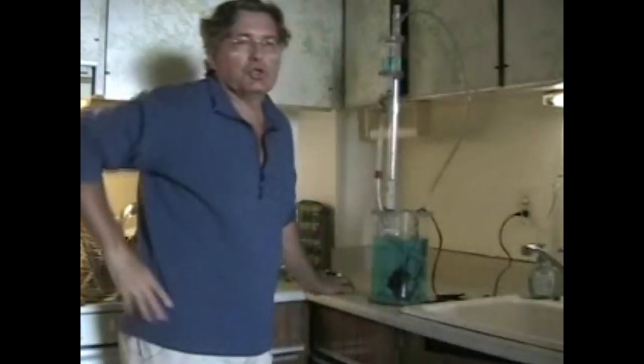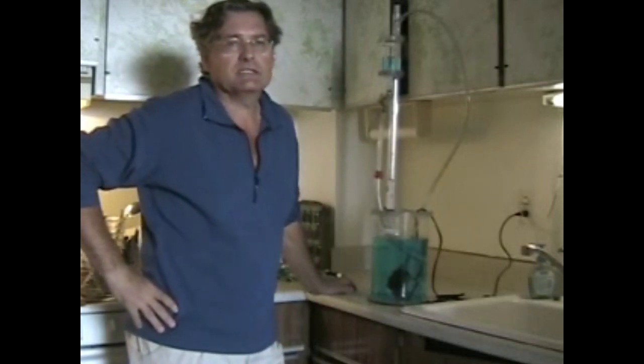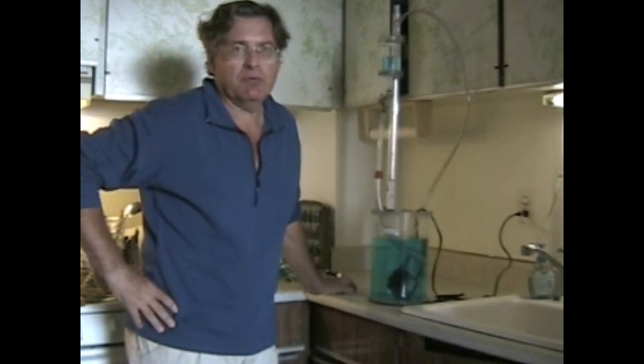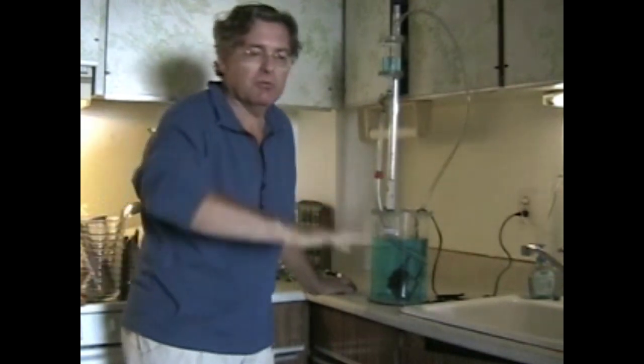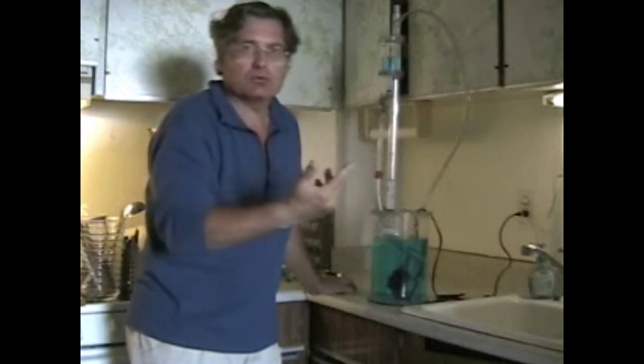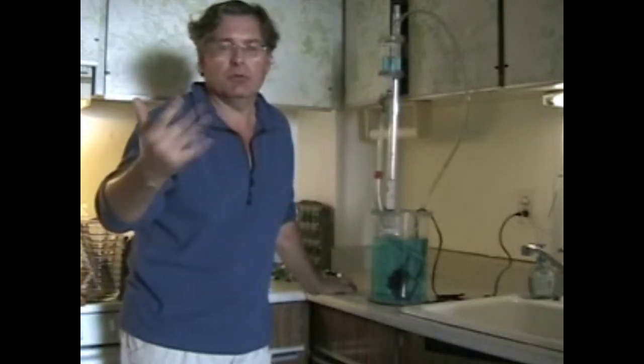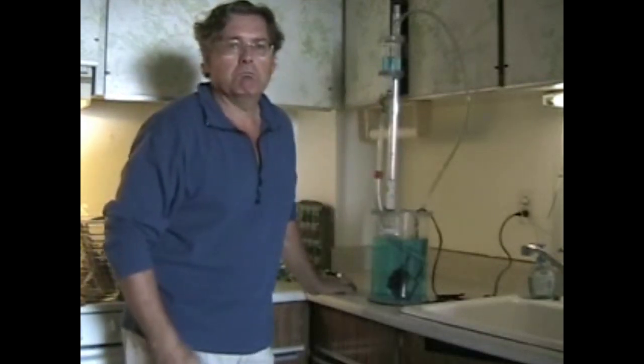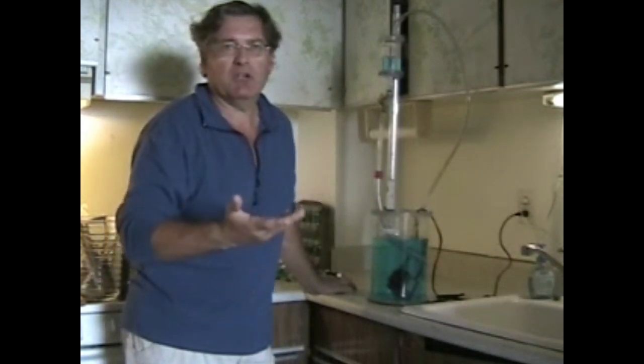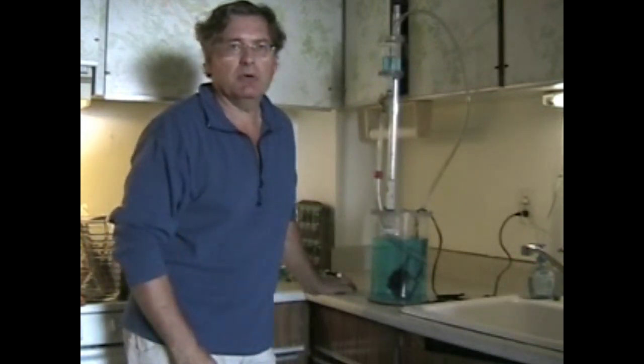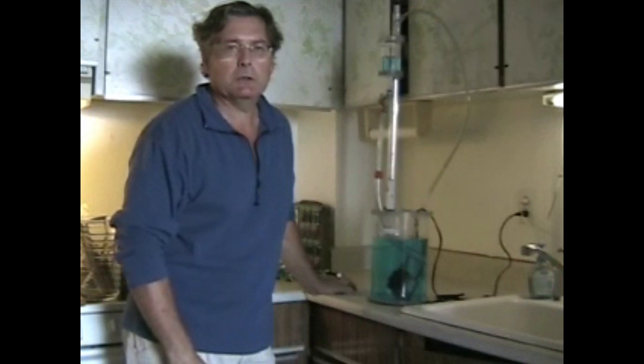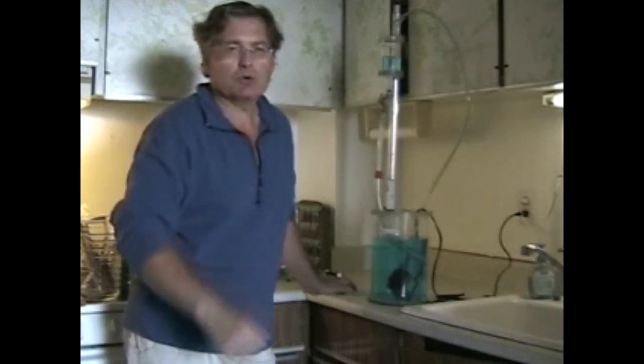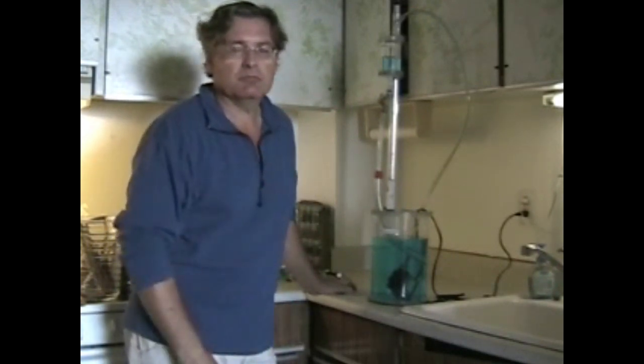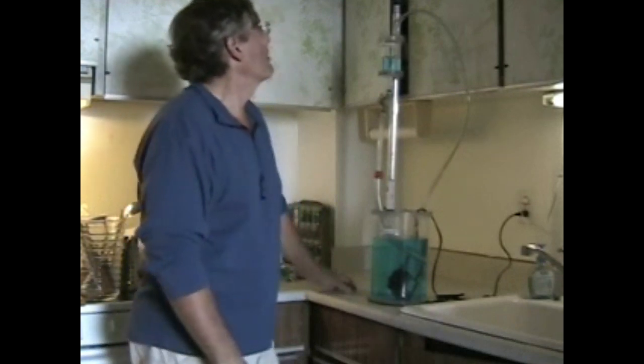This experiment shows the formation of vortexes in a suction tank. If the flow is high enough and the depth of the suction tank becomes low enough, a vortex will form and air will be entrained into the pump, and this combination of air and fluid won't pump as well, and the flow rate will drop, so that there will be a disturbance in the process.